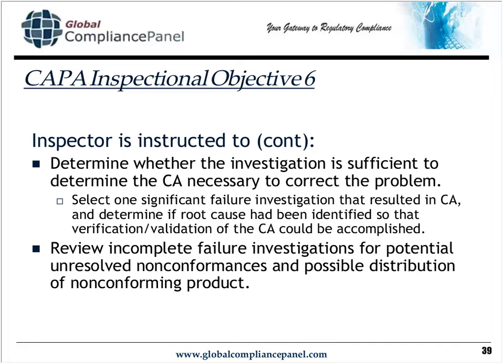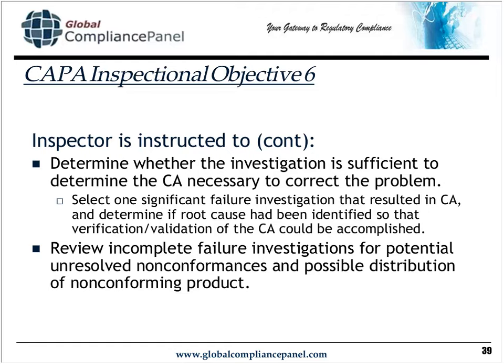So they're going to look at one significant failure investigation. The way they determine significance of failure investigations is just one that resulted in a corrective action. And they're going to look at root cause, and then they're going to look at verification or validation of the corrective action. And for any failure investigations that they determine to be incomplete, they're going to look at whether there are any unresolved nonconformances, and whether you distributed any nonconforming product because of these unresolved nonconformances and incomplete failure investigations.